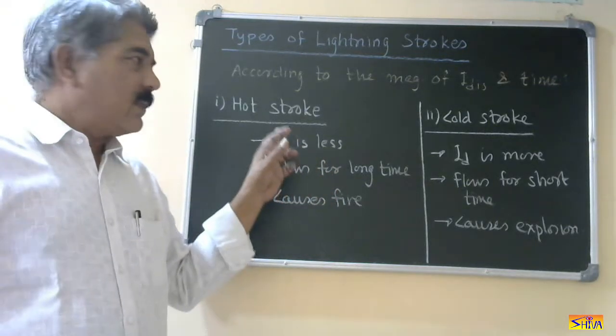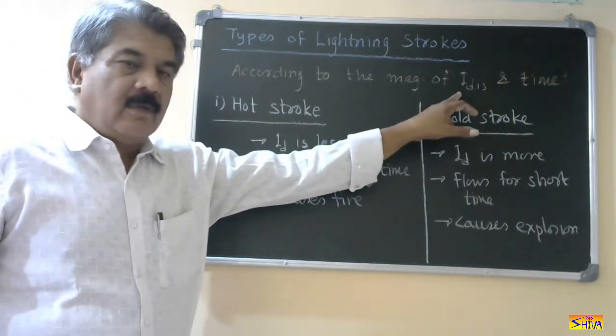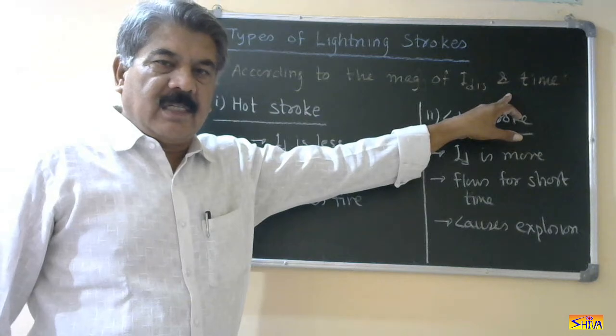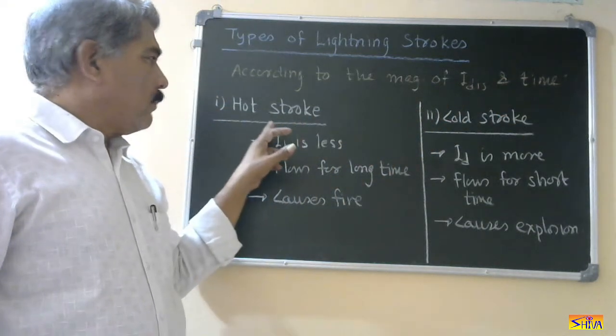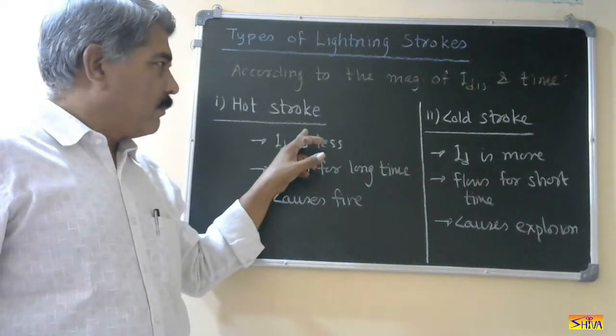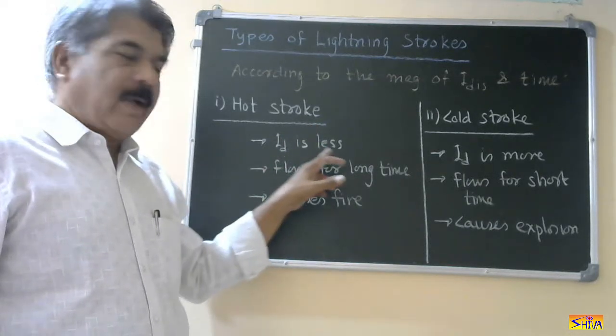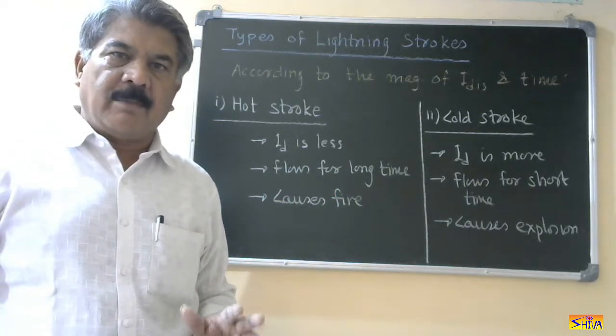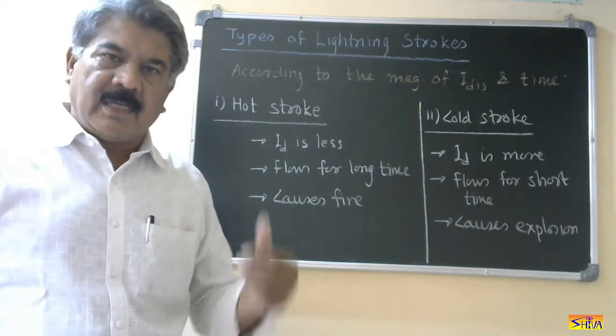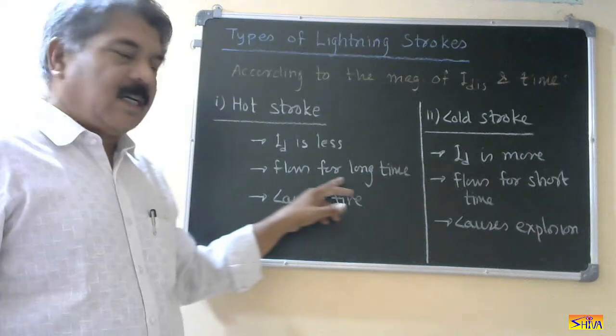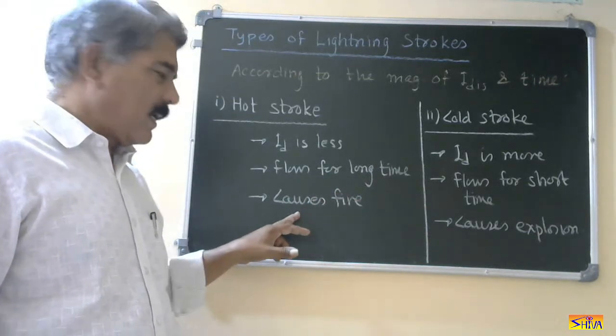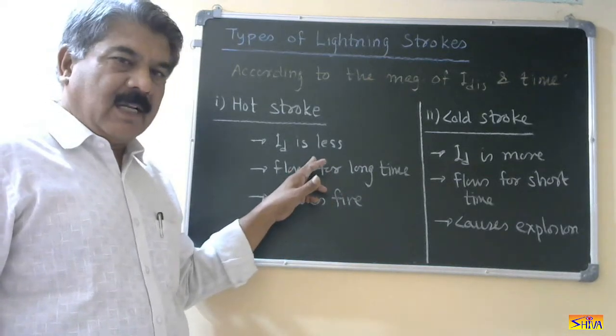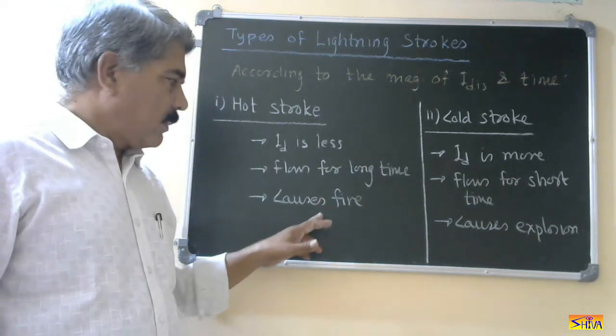The next classification is according to the magnitude of the lightning discharge current and the time for which this discharge current flows. The first classification is hot strokes. Hot strokes are characterized by a low magnitude of discharge current. Please note that low magnitude here does not mean milliamperes or amperes — it is in kiloamperes, but relatively less current. This current flows for a long time, and its characteristic effect is that it causes fire when it strikes the object.